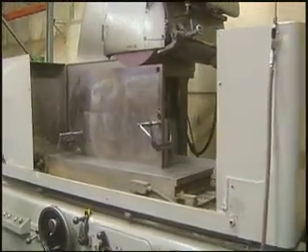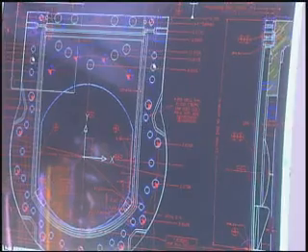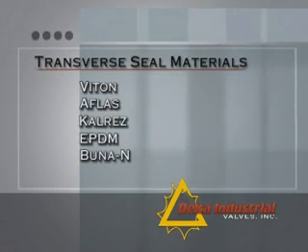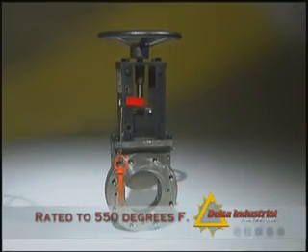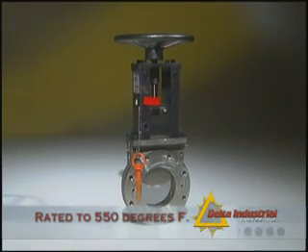Delta Industrial's valves are produced at its modern manufacturing facility in Niles, Michigan. Delta's engineers custom design valves of all sizes and in a variety of materials. Seals are available in, but not limited to, VITON, AFLAS, Kalrez, EPDM, BUNA-N, and Teflon. Delta Industrial's knife gate valves with elastomer seals are used up to 550 degrees Fahrenheit, and other seal materials are available for higher temperature applications.